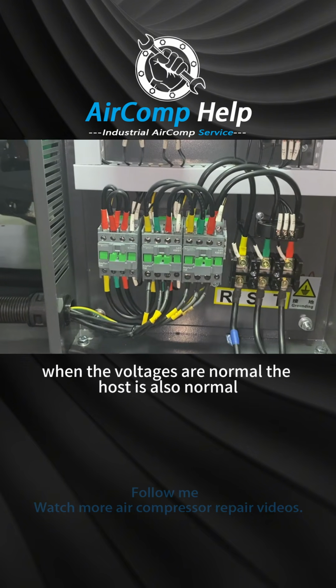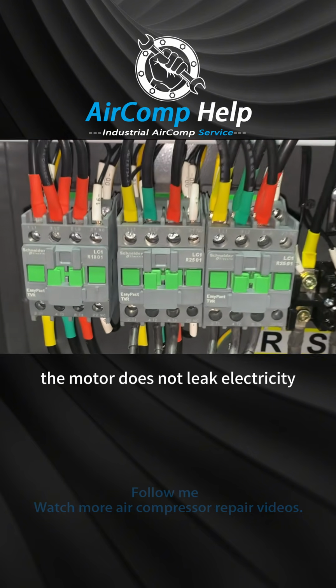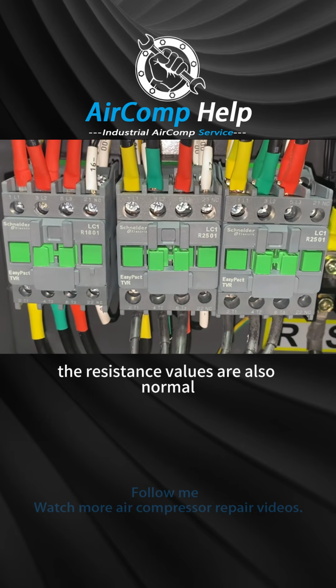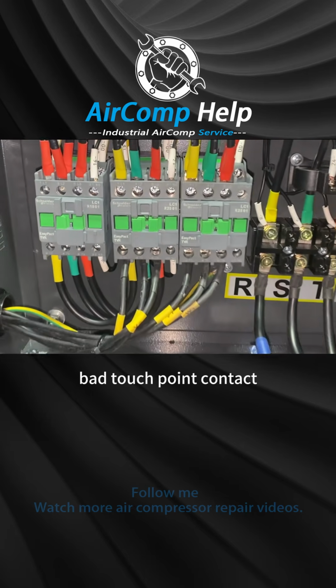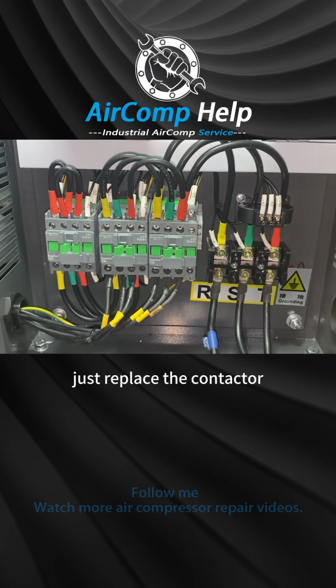When the voltages are normal, the host is also normal, the motor does not leak electricity, and the resistance values are also normal, then there's the contactor problem, bad contact points. Just replace the contactor.